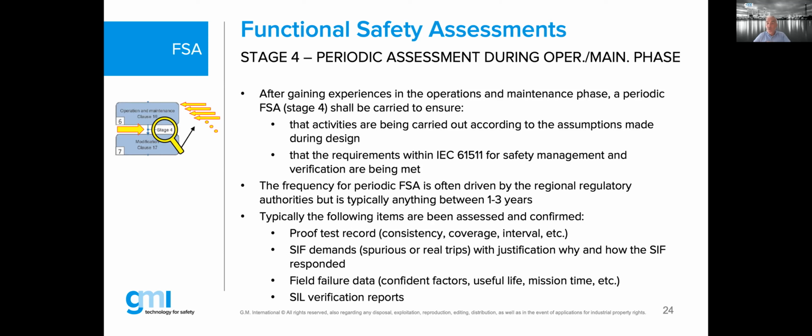I can tell you now, if you start to do this type of investigation as an expert judgment, how often do we come across an end user that today has no record on the useful life of his final element, call it the shutdown valves. As long as the valve is moving or working when it is required to work, everyone a happy family.